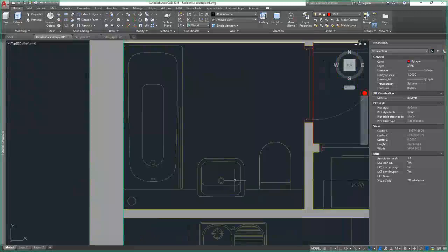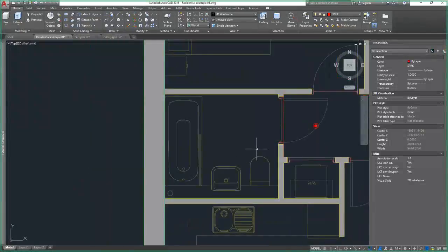Let's have a look at this bathroom now. Do we need to protect the bathroom? Well, again, if it's smaller than 5 square meters, then we don't have to. So let's have a quick look. This is 1.98 times 2.15. So that is 4.2 and a bit. So again, it is smaller than 5, so we don't have to sprinkler protect it.